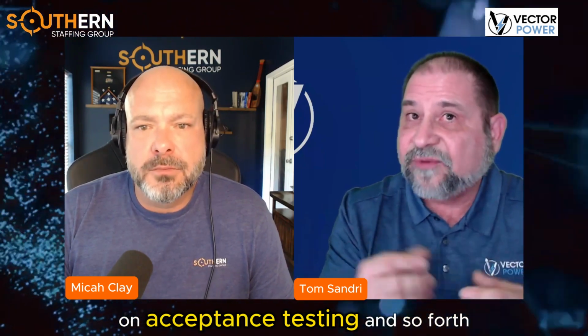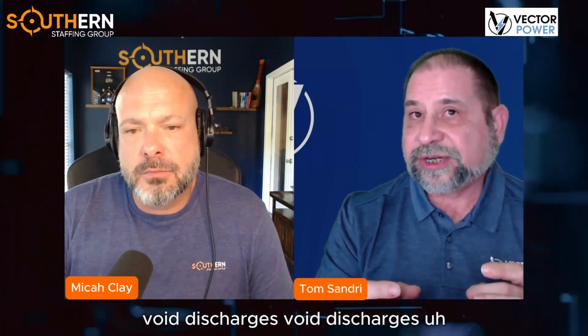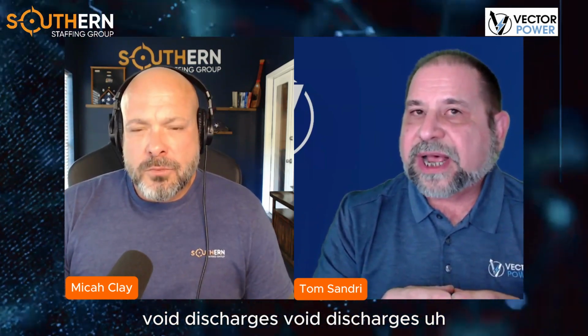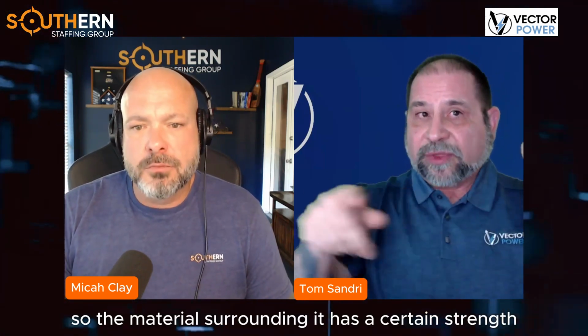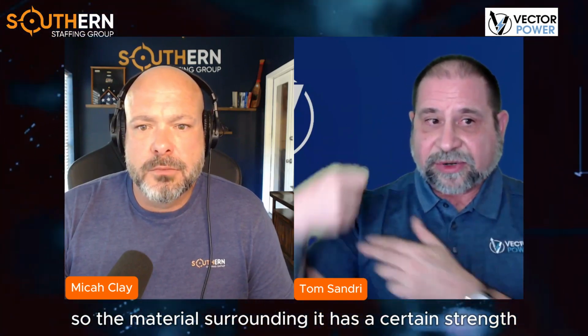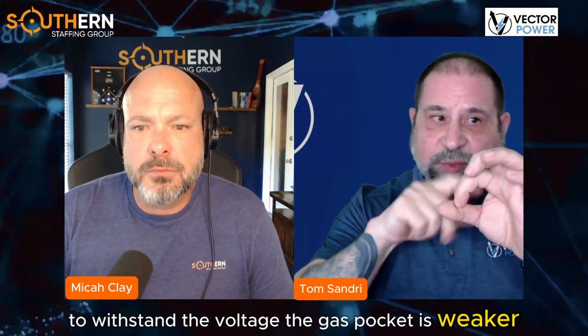And then probably the other one, particularly when we're doing a lot of the testing of the cables on acceptance testing and so forth, void discharges. Void discharges typically is where, picture you have a chunk of insulation, and inside the block of insulation you have a gap, a void, a gas pocket or air pocket. So the material surrounding it has a certain strength to withstand the voltage. The gas pocket is weaker.